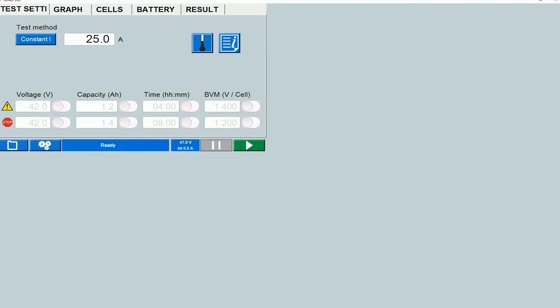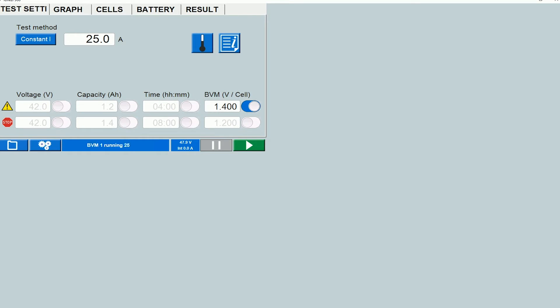So the fourth parameter, you can set limits based on BVMs only if you're using BVMs as accessories. A typical way to go about it would be to set a warning limit on the individual cell voltage and again this is only possible if you're using BVMs. So let me just enable it. You can see that the value is 1.4 volts here.